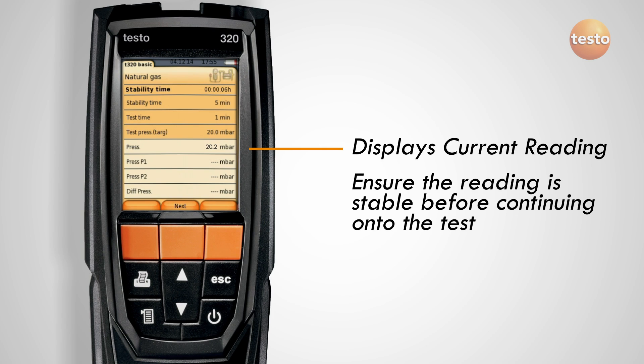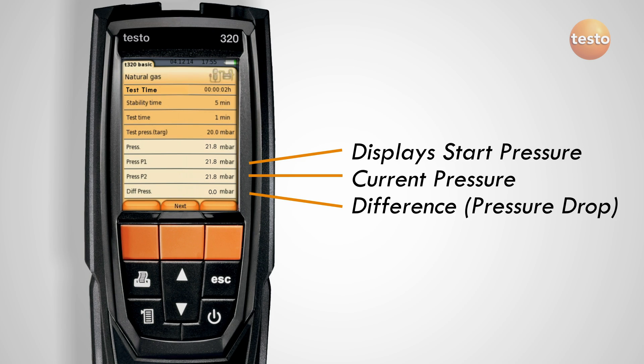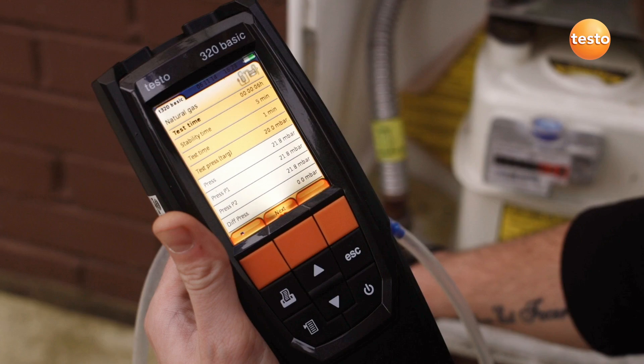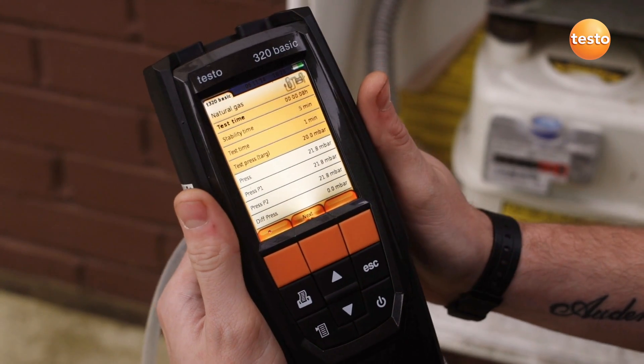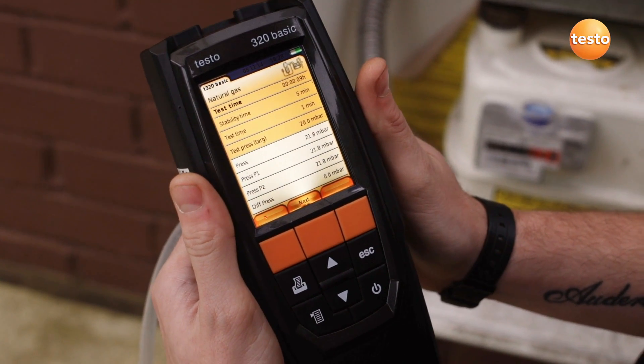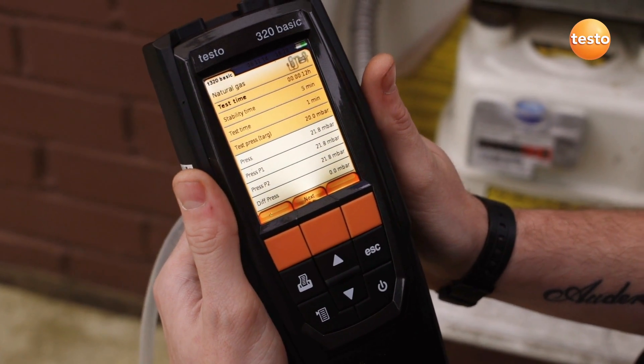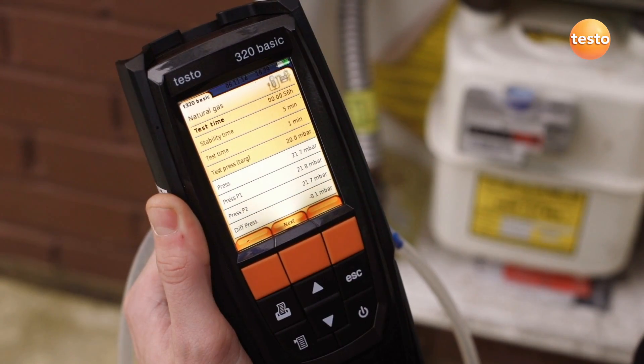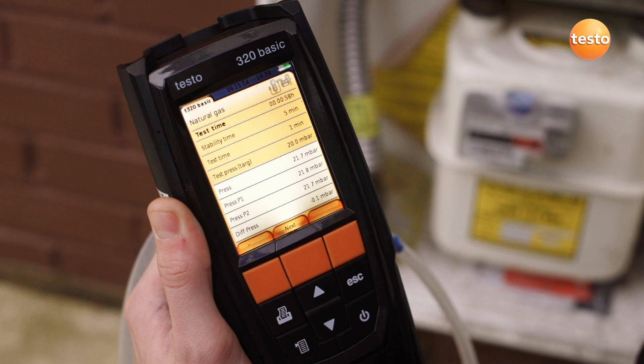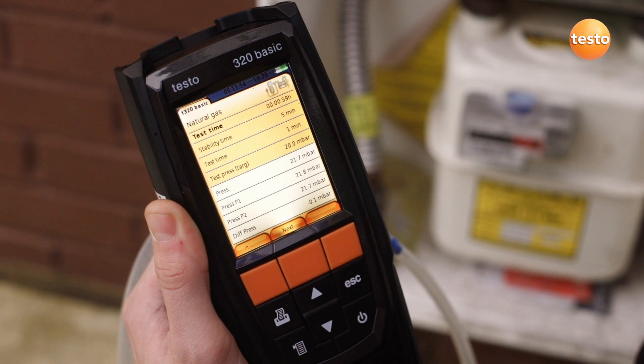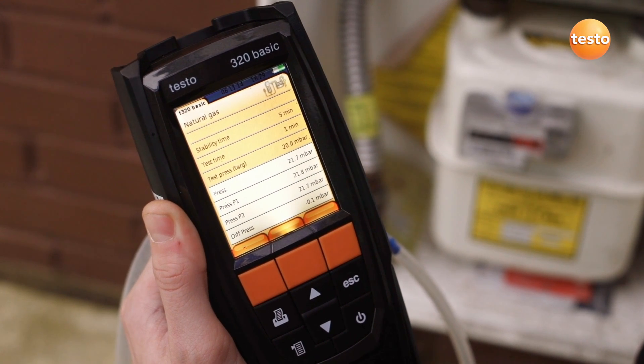Industry standards originated for carrying out the tightness test with the U gauge and say there should be no discernible pressure drop during the tightness test. Using a flue gas analyzer or digital manometer, the maximum pressure deviation is 0.2 mB, which is the value the industry accepts as a discernible drop. At the end of the test time, the results are automatically logged.